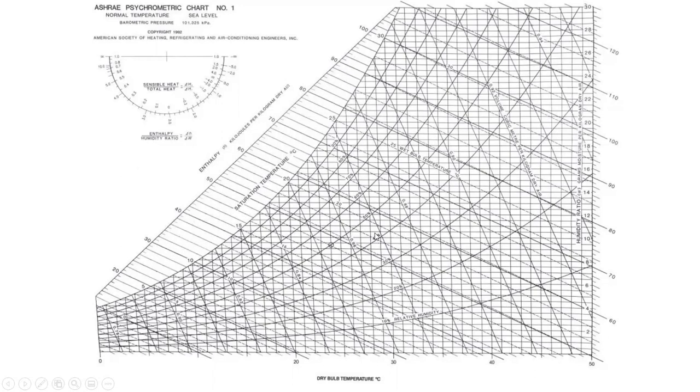These sweeping lines are relative humidity: 10%, 20%, 30%, 40%, all the way up to 100% — that's the saturation curve. Hot air can hold much more moisture than cold air, so 100% relative humidity at a cold temperature may not have much water in it, whereas air at 45°C at 20–30% relative humidity would have far more moisture. That's why when we work problems, we try to get out of relative humidity units into a more absolute measure like humidity ratio.